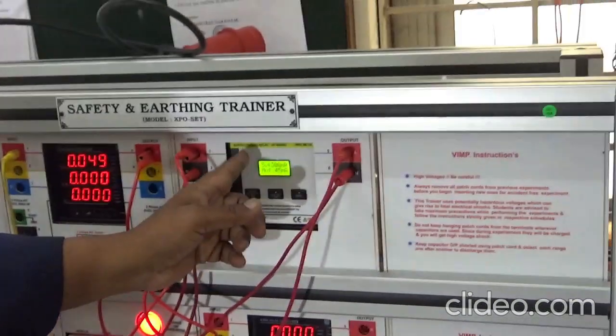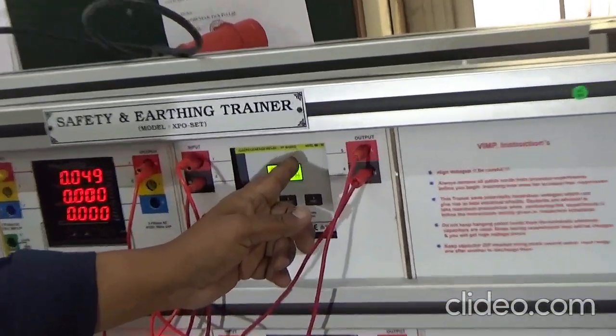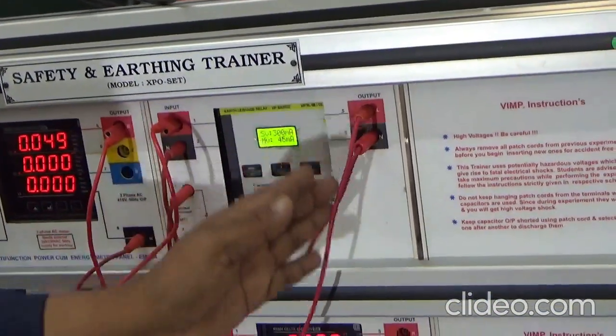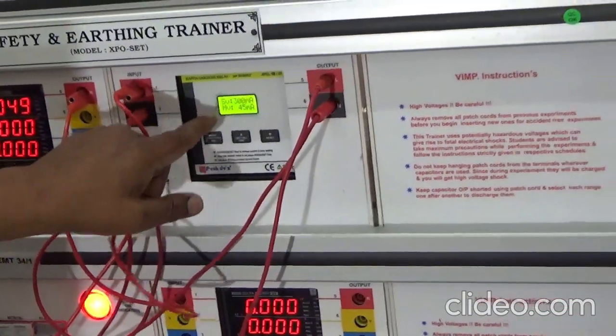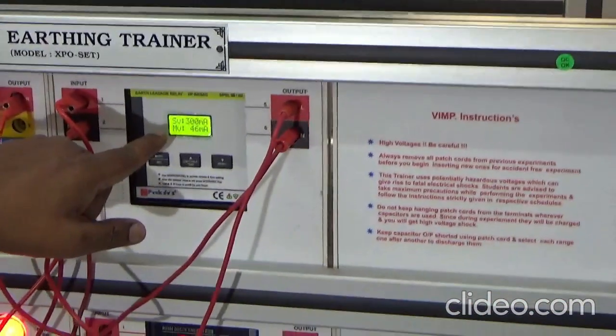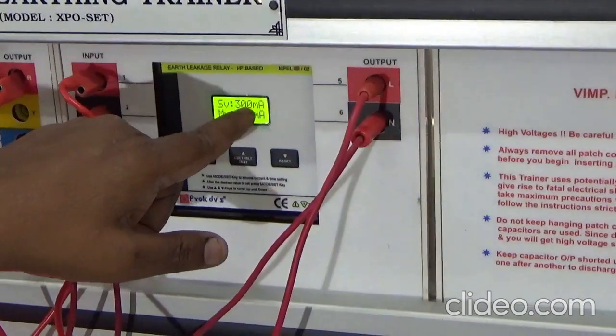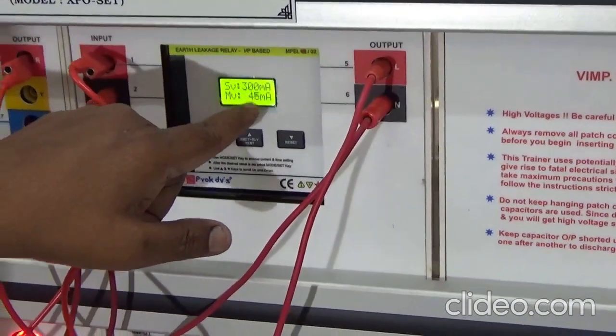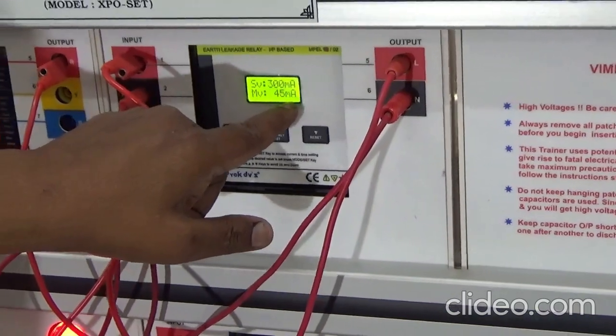Similarly, we have an earth leakage relay. It is a microprocessor based earth leakage relay. It shows SV and MV. SV stands for set value, MV stands for measured value. Right now my engineers have set 300 milliampere. It is showing MV as 46 milliampere.